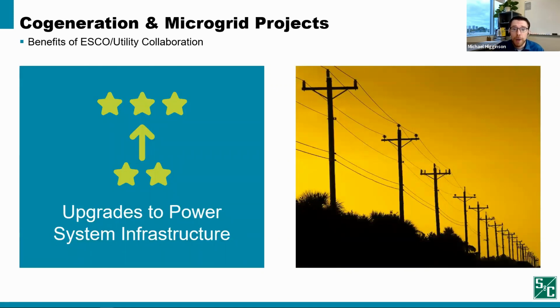Often cogeneration and microgrid projects require upgrades to the local power system infrastructure. For example, these upgrades can include protection improvements, such as directional power measurements at the point of interconnection to measure for exports, or direct transfer trip signals sent by the local utility and received by the microgrid to ensure generation is disconnected if there's a local system fault or a switch opens, avoiding undesirable islanding conditions.